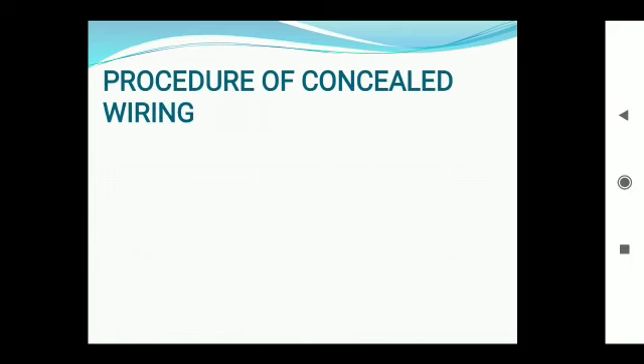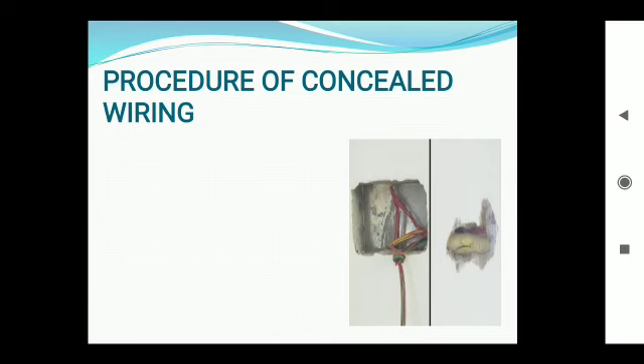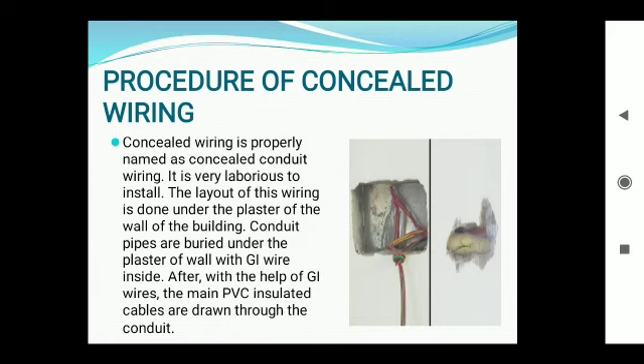Now the procedure of concealed wiring. You can see the image of a concealed wiring. Concealed wiring is properly named concealed conduit wiring. It is very laborious to install. The layout of this wiring is done under the plaster of the wall of the building. Conduit pipes are buried under the plaster of the wall with GI wires inside. After that, with the help of GI wires, the main PVC insulated cables are drawn through the conduit. It means GI wires are used to pull the phase and neutral wires. So GI wires are used for two purposes: one is to pull the wires and another is as an earth wire.